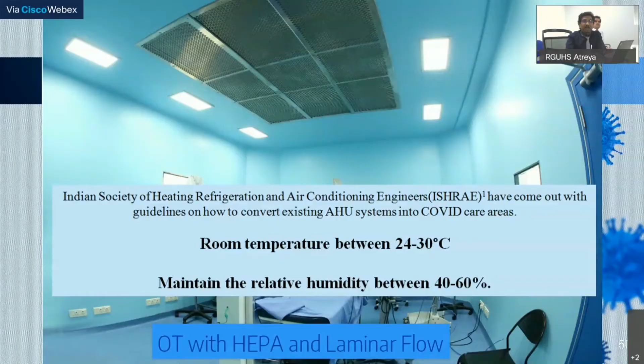I know many ophthalmic practitioners in small towns and remote places have split ACs. It is not recommended to use these during these times, as they are pure recirculation units. However, you can consult AHU experts and try to add fan filtering units with HEPA, and also an additional powerful exhaust fan with HEPA, with ducting to release the exhaust at least 3 meters above the highest point of your building. This can be considered after talking to your AHU expert.